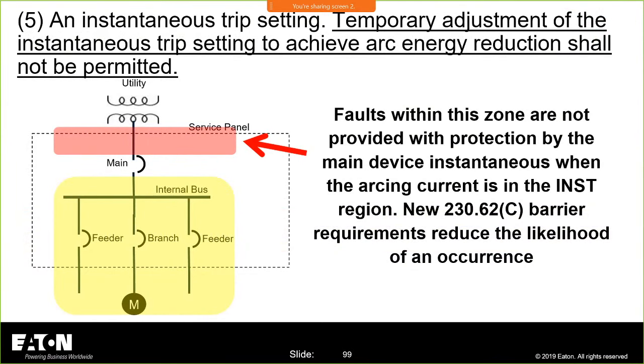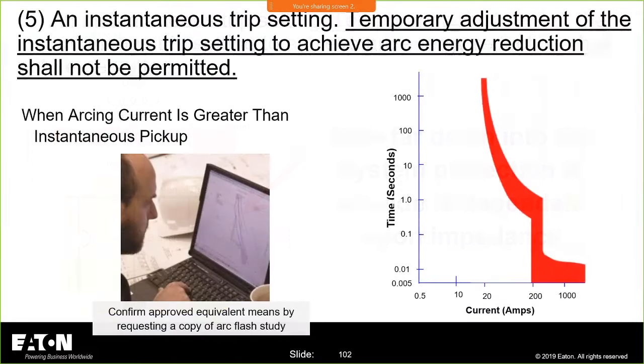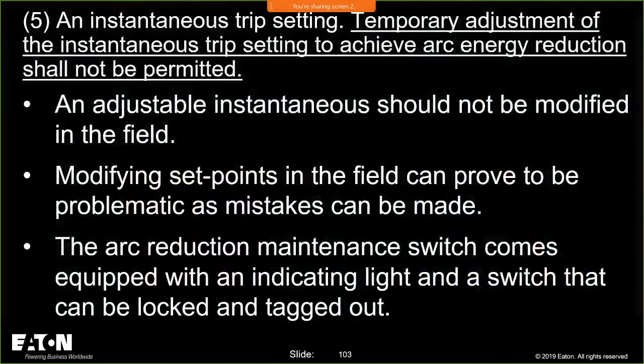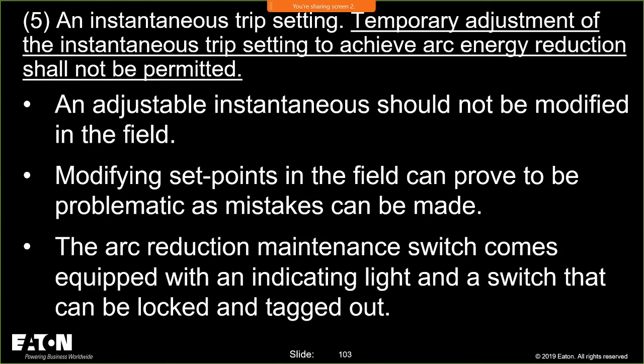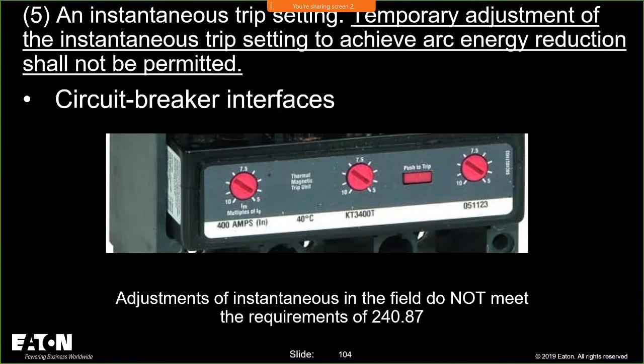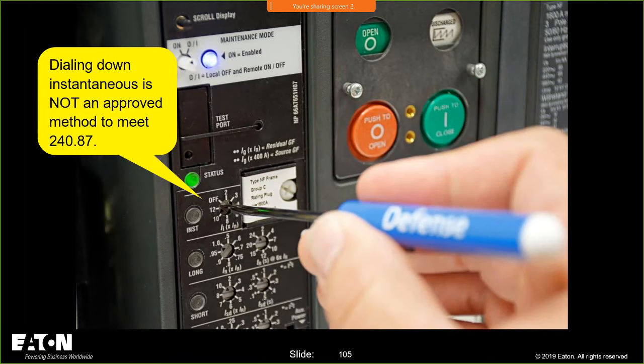You can't field adjust the instantaneous. Again, that's your instantaneous. Adjustable instantaneous should not be modified in the field. You take a look at the different types of devices in the marketplace. A person looking at this might not realize. They might think that the one on the left is the long time, the one in the middle is the short time, and the one on the right is the instantaneous. No, all of those are instantaneous. All three of those dials are instantaneous pickup only. Dialing down the instantaneous is not an approved method to meet 240.60, 240.87. That is not a good thing.